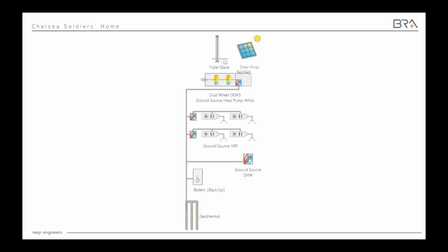So in this case, we do have a geothermal loop, about 145 boreholes, 500 feet deep each. And that geothermal loop water, it's a closed loop system. It circulates between the ground loop and the building loop. And then the building loop goes to all of these different pieces of equipment that can pull heat out of that loop in the winter or reject heat into that loop in the summer.